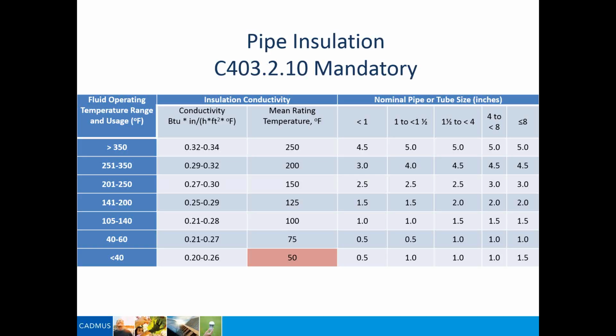And you would go to this table. So for a boiler system for domestic hot water, you'd go to this table, and if you're running your hot water, let's say, between 105 to 140 degrees, you would have to insulate those hot water lines. So this looks at piping insulation for both cooling systems and hot water systems in your particular climate. Here we also worry about boiler temperatures for heating, so we'd have to insulate. But from your standpoint, you're pretty much looking at just cooling and domestic hot water.